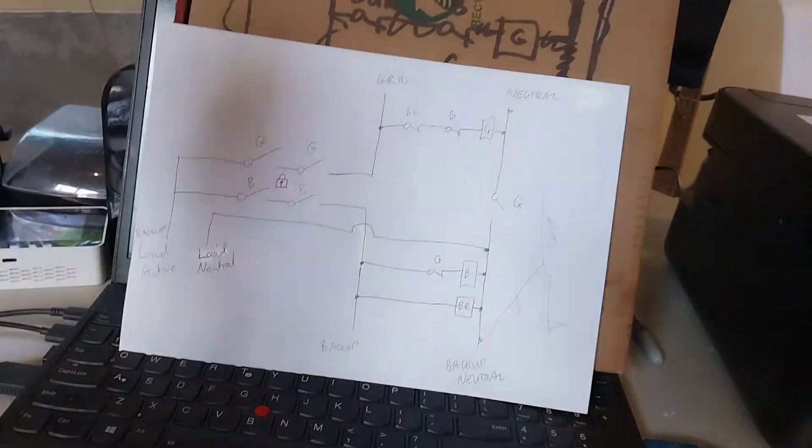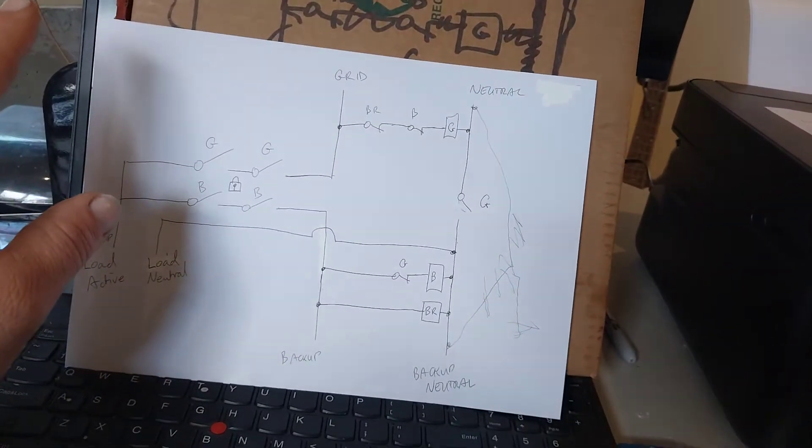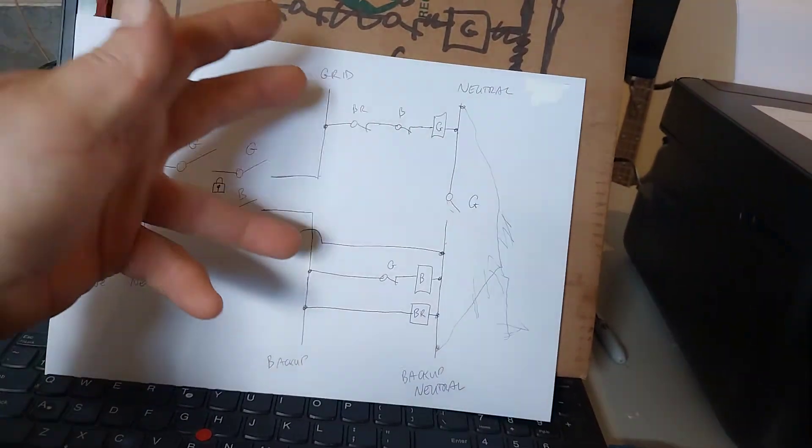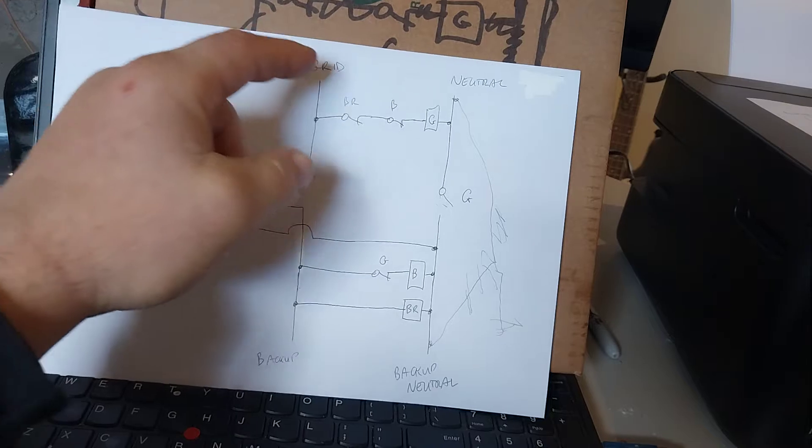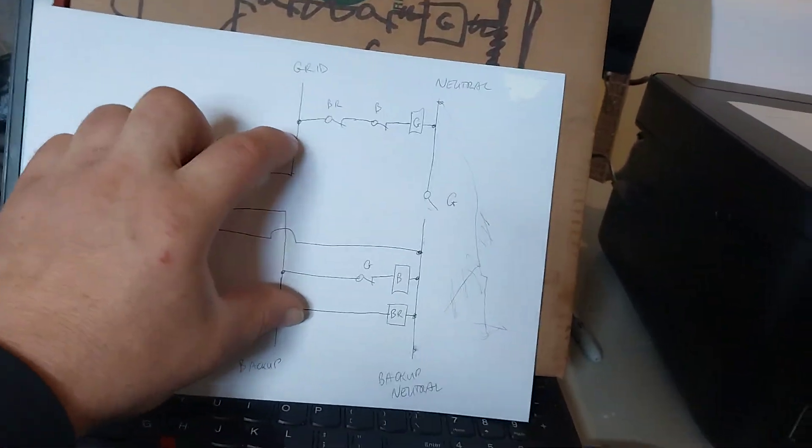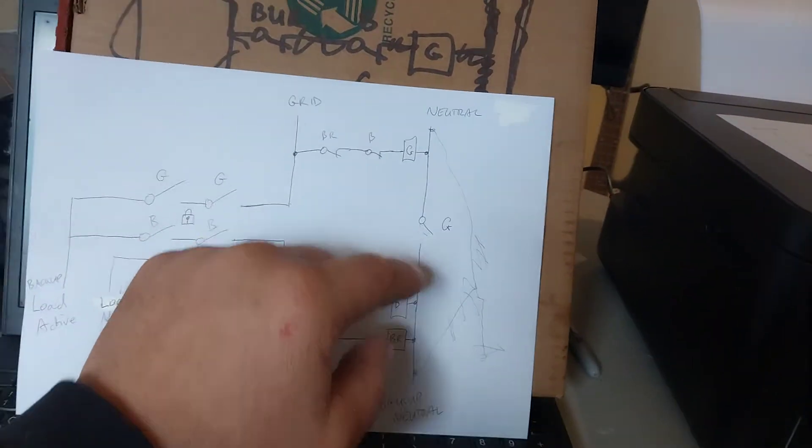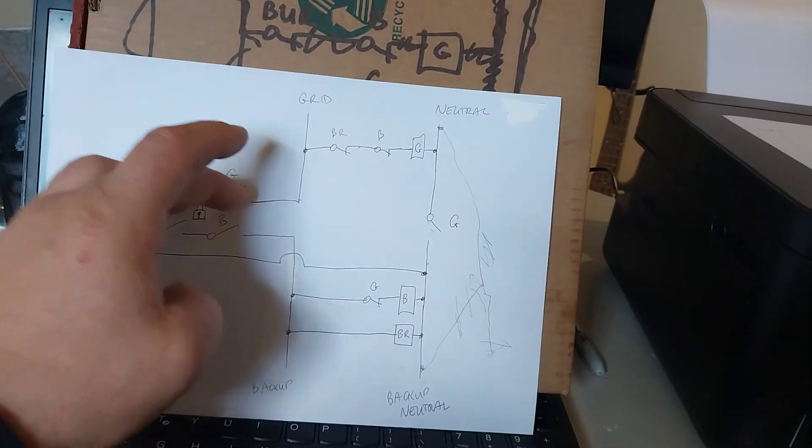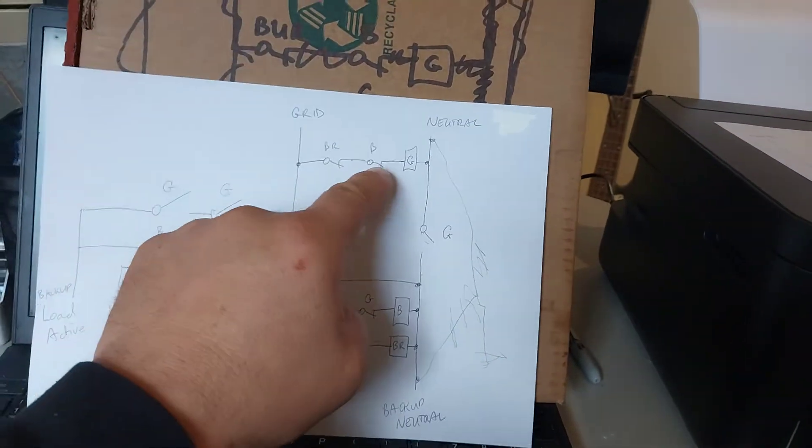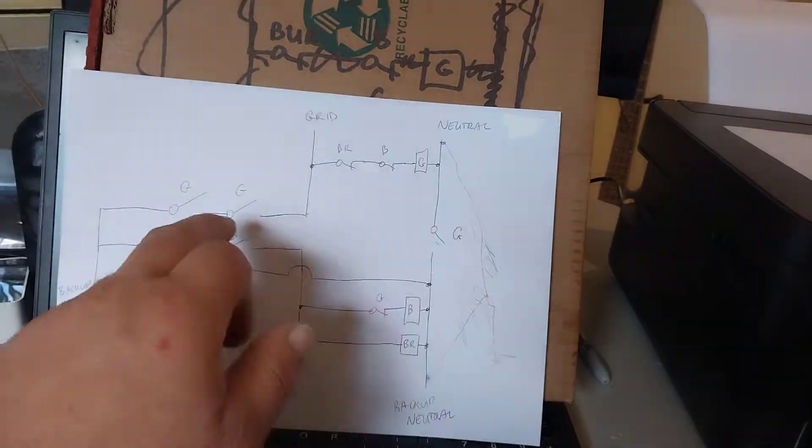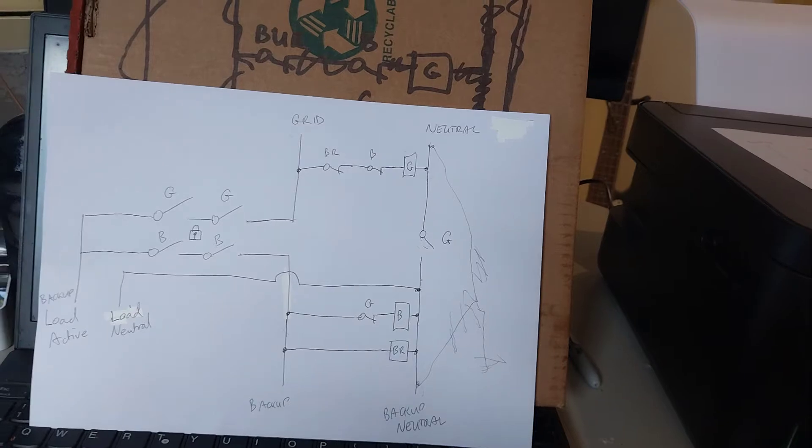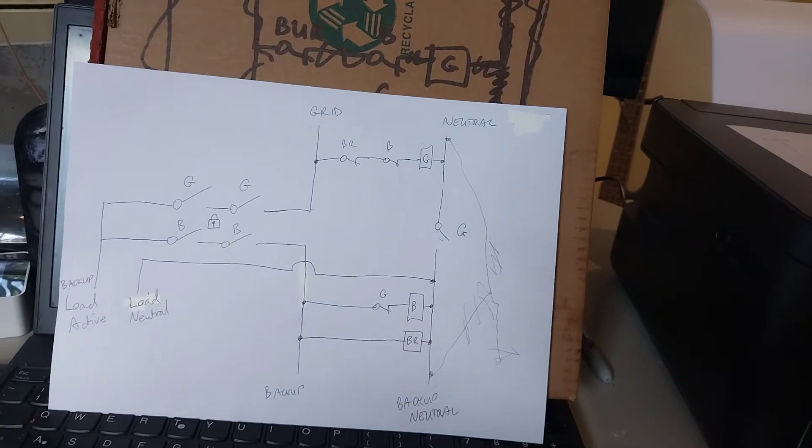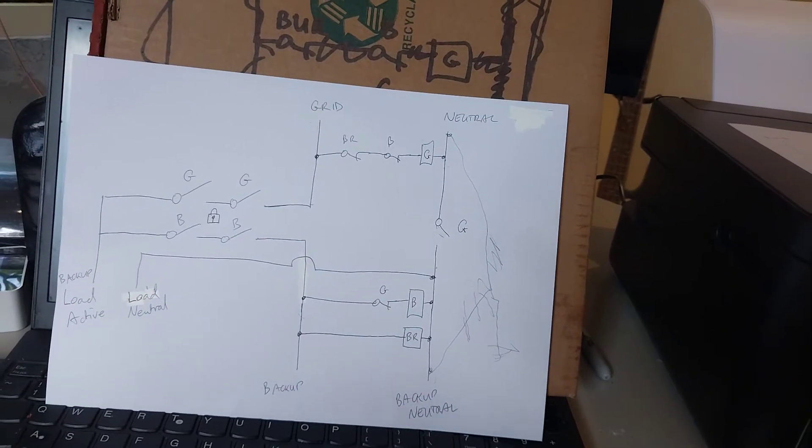And the only thing now is what we need is priority. If these were turned on identically at the same time, grid and backup power supplied, these will be racing to whichever one could be first to pull in and block the other one out through its interlock there. And mechanical as well. So we don't want a race between the two. We want priority.